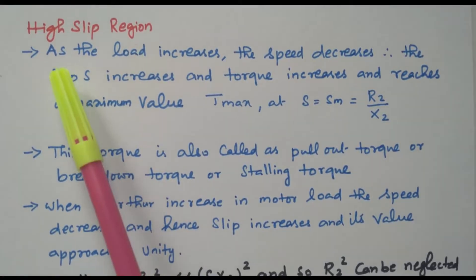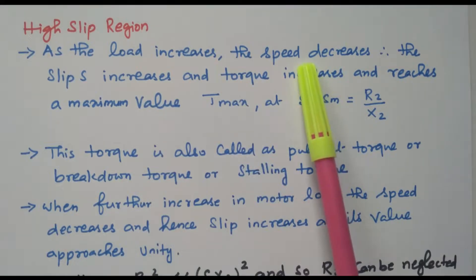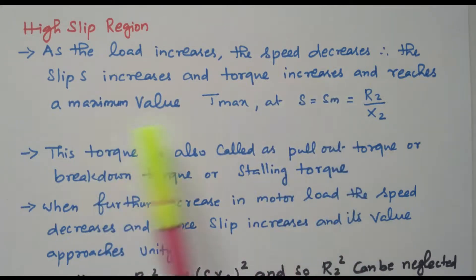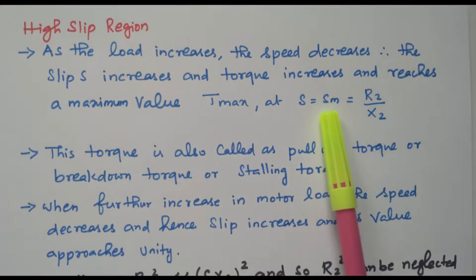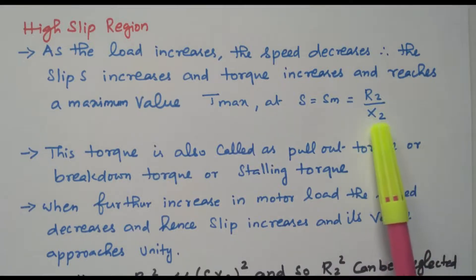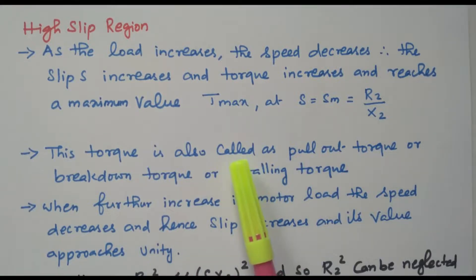During the high slip region, as load increases, speed decreases, and slip increases. The torque increases and reaches the maximum value at S equal to S_M, where the condition is R2/X2. This is the condition for maximum torque. As load increases and speed decreases, slip increases, and torque reaches the maximum value. This maximum torque is called the pull-out torque, breakdown torque, or stalling torque.